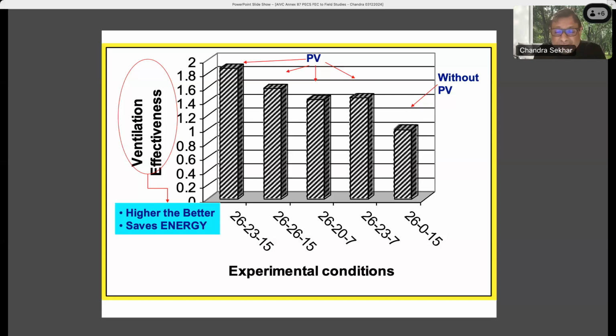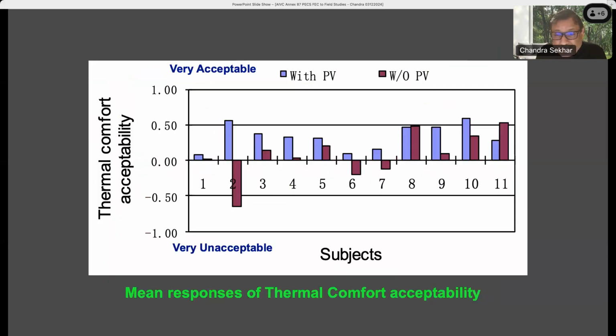Now, obviously, we'll notice that if you have a warm background - say, the first bar, background at 26 degrees, and personalized at 23 degrees - you get the highest ventilation effectiveness. That says a lot about the potential to save energy, because the warmer the background temperature in our application, which is hot and humid, the better it is from an energy point of view. And of course, higher effectiveness means it's much more beneficial for comfort and indoor air quality considerations.